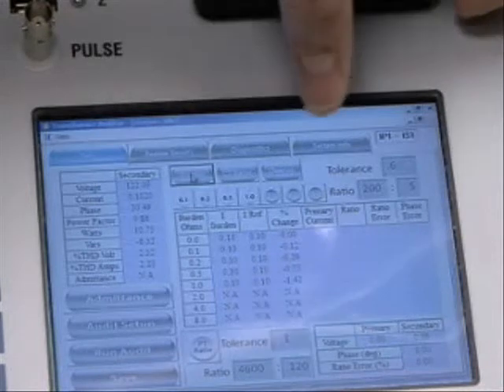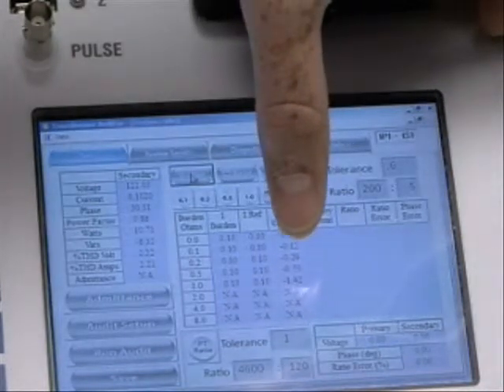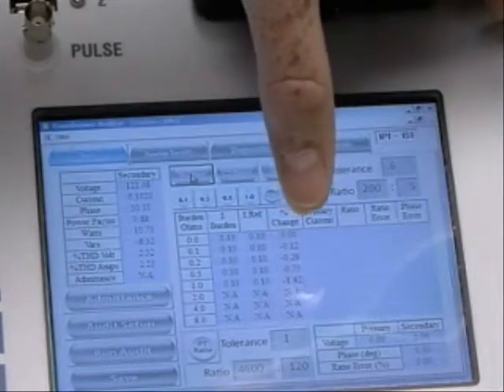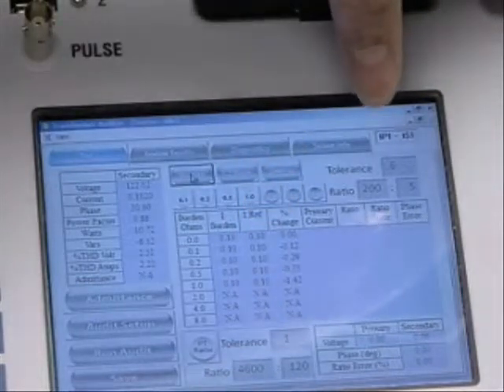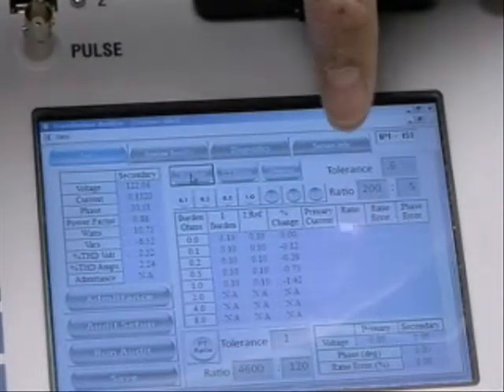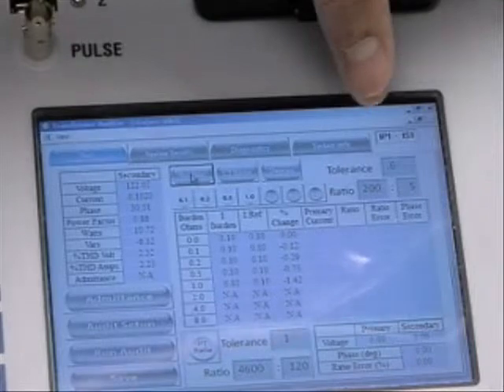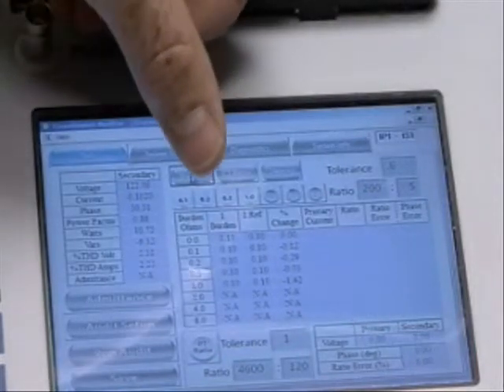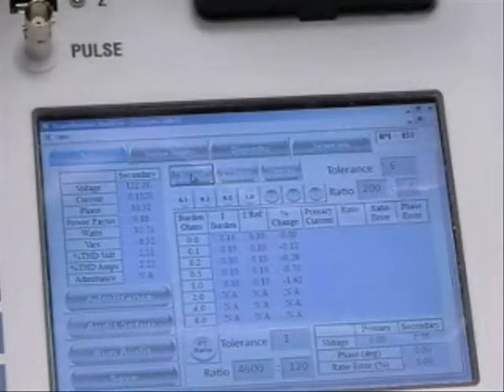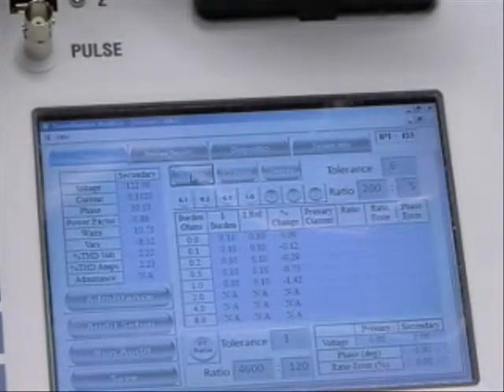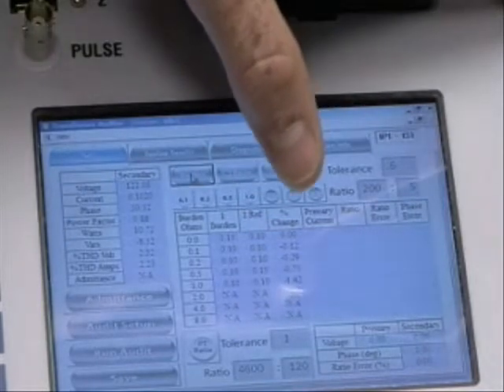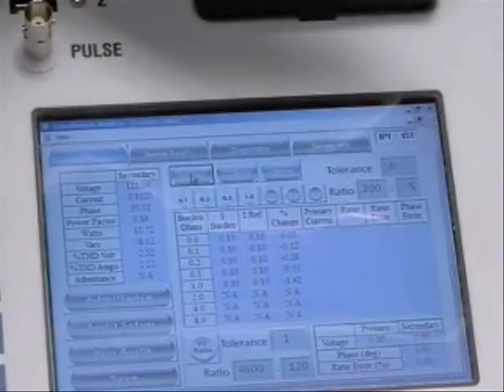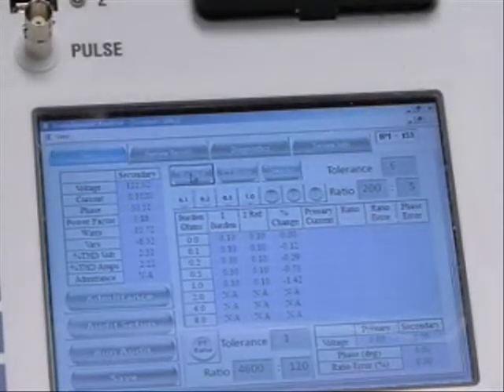And in this case, all the values except the 1.0 burden, and even the 0.5 ohm burden, are underneath the 0.6% tolerance, which is really good. What a burden test is actually doing is trying to determine how much burden might already be in the secondary loop of that test output of the CT. And in this case, everybody's passing underneath the 0.5 ohm burden, which is expected. So this is a great burden test.